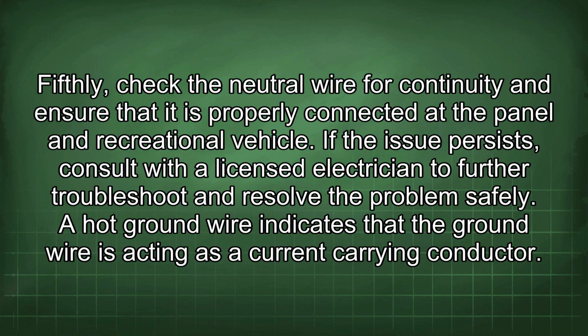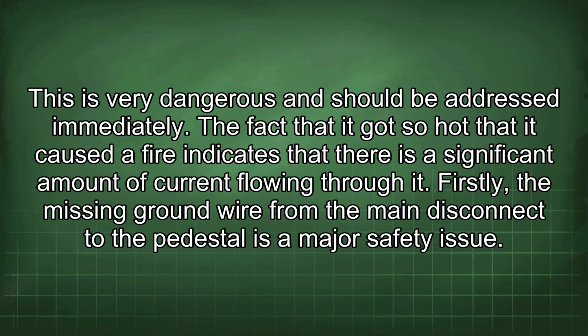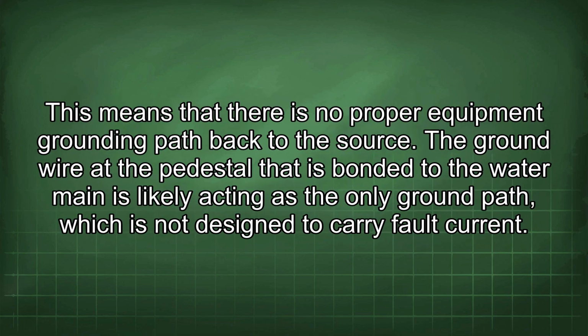safely. A hot ground wire indicates that the ground wire is acting as the current carrying conductor. This is very dangerous and should be addressed immediately. The fact that it got so hot that it caused a fire indicates that there is a significant amount of current flowing through it. Firstly, the missing ground wire from the main disconnect to the pedestal is a major safety issue. This means that there is no proper equipment grounding path back to the source. The ground wire at the pedestal that is bonded to the water main is likely acting as the only ground path, which is not designed to carry fault current.